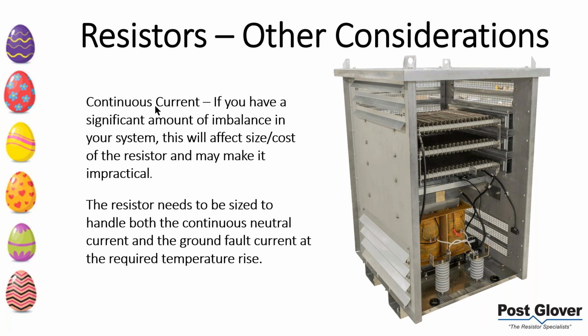If you have a lot of continuous current, now if you have a significant amount of imbalance in terms of percentages, 5 or more, I would say more than 5%. Some people load 10%. I think that's way high, but that's their call. But the point is that if you get a lot of continuous current, that's going to make this harder as well, because you're going to have that additional continuous current flowing on top of the ground fault current, which you'd have to be able to handle both of those at the same time under the same temperature.